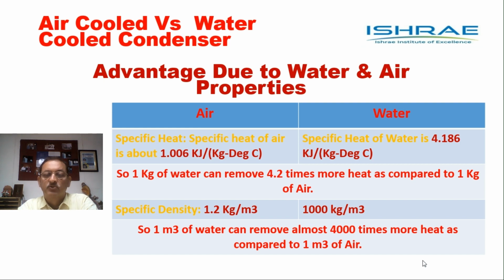The other property that I would like to talk about is specific density or gravity of air and water. The specific density of air is 1.2 kilograms per meter cube approximately, whereas that of water is 1000 kilogram per meter cube. And so, if we consider volume wise, because we have to handle volume, 1 meter cube of water can remove almost about 4,000 times as much heat as can be removed by 1 meter cube of air. Now, there is a massive amount of difference. The size of fan that will be needed for moving that much of air will be much larger, and the power consumption that will be needed for moving air will be much more as compared to the power consumption that will be required to move water.